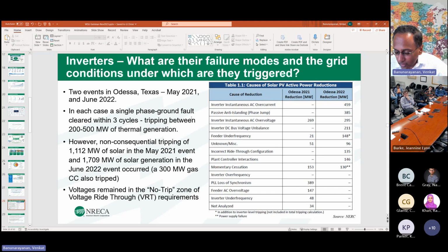A simple example some of you may have heard of: two disturbances in Texas, May 2021 and June 2022. In each case there was a single phase to ground fault that cleared, but then a bunch of inverters tripped, over 1,000 megawatts of solar generation. What were the reasons for tripping? This table from NERC shows, for each disturbance, how many megawatts tripped due to each reason.